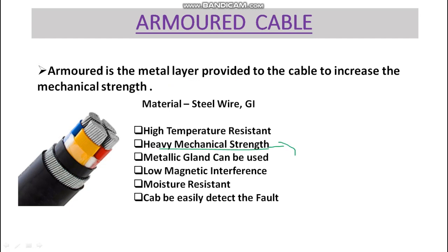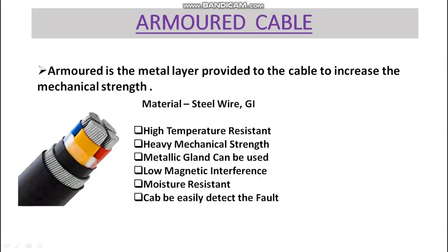Another major advantage is heavy mechanical strength. This is the most important advantage. We commonly use armored cable for underground installations. During maintenance, excavation, or digging above the cable, if any equipment — such as an excavator or spade — hits the cable, the armor protects it from damage.